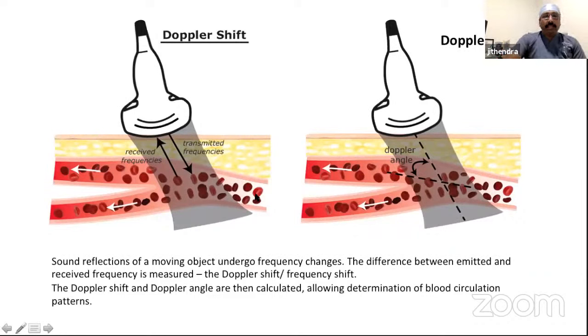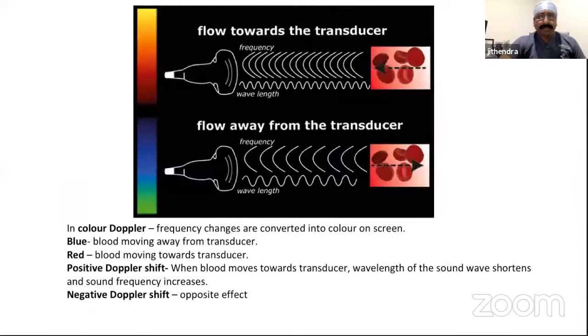There's something called Doppler shift as well as Doppler angle. What you see here is blood flowing from the right to the left, and you see the transducer over the tissue. Sound reflections from moving objects undergo frequency changes. The sound waves are reflected off the RBCs that they strike, and the frequency which returns is different. So there's a difference between the emitted and received frequency, which is measured, and this is called the Doppler shift or frequency shift. The Doppler shift and Doppler angle are then calculated, allowing determination of blood circulation patterns. We'll see a video on that after this.